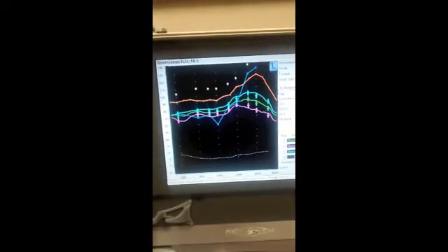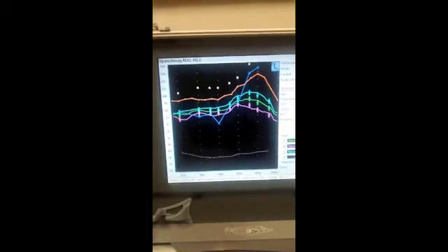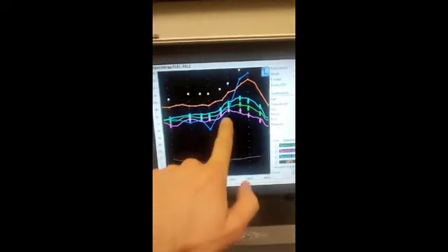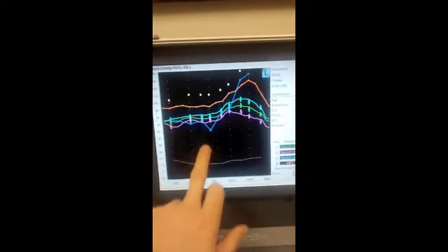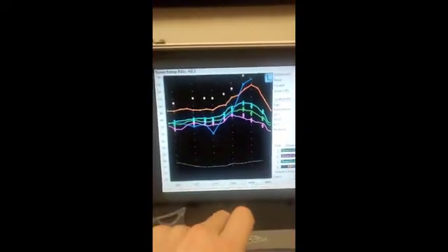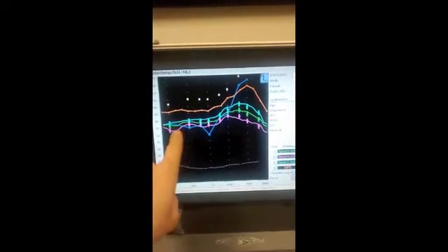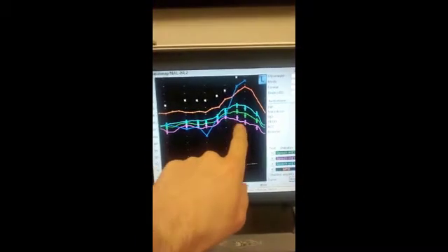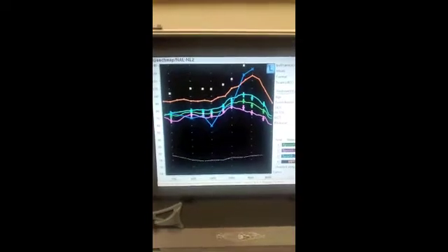So on this machine, this is the machine that verifies what the hearing aids are doing. How are they actually amplifying? And in this machine here, I've inputted the patient's audiogram, their hearing test. So on this graph, everything below the patient is unable to hear. After I've inputted these results, I'm given these crosses, sorry, that tell me how much I should amplify at each different frequency region.